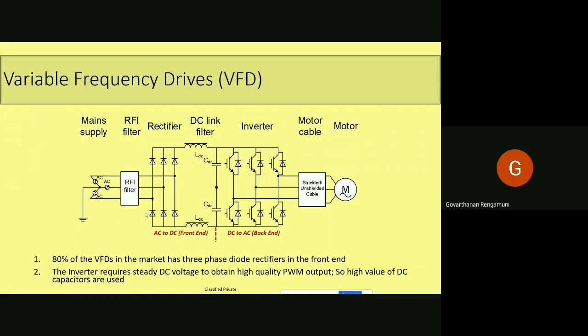VFDs are the predominant devices connected to the grid because they are always rated high power. It ranges up to 1.10 megawatt also. So the pollution is majorly due to VFD kind of converters, and 80% of the VFDs in the market have three-phase diode rectifiers in the front end. So this example is considered. This will be very helpful for understanding the harmonics, the effects of harmonics at the grid, and mitigation techniques.